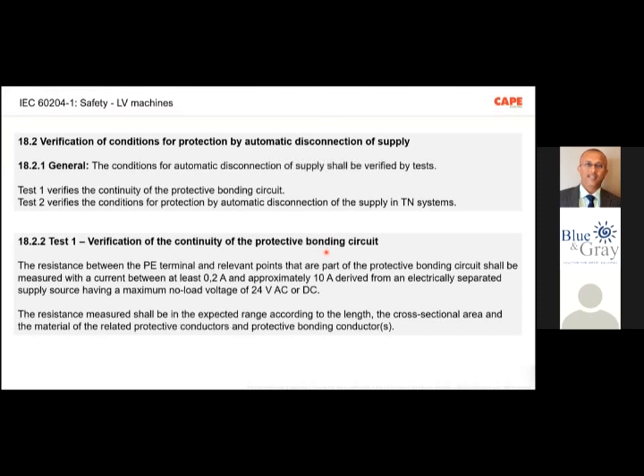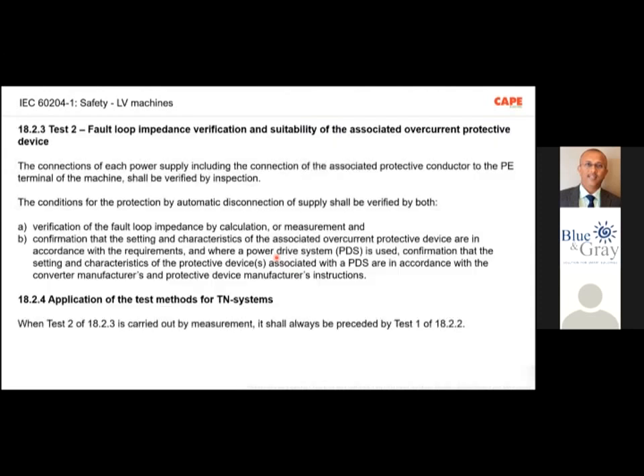It means different metal parts in your building are connected by metal wire so that no potential difference exists in that building. That is the basic idea. So this is verification of continuity of protective bonding circuit. That means you have a wire which you are using for this connection, you measure the resistance of that wire, and you compare it with the reference. Number two is fault loop impedance and verification of suitability of the associated overcurrent protective device. So this is test number two. Both these tests I will show with video so that you will be able to understand them better.